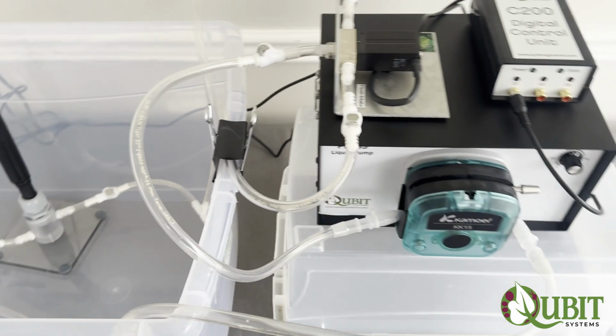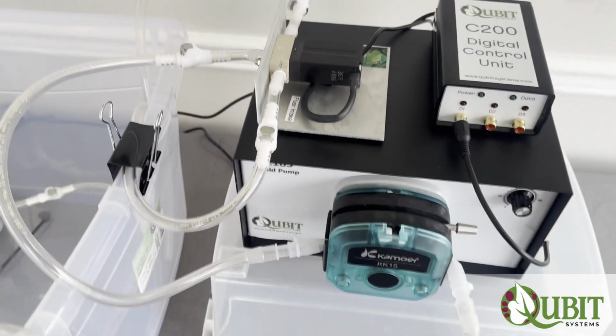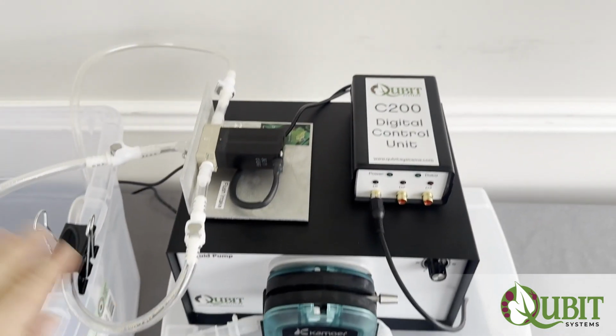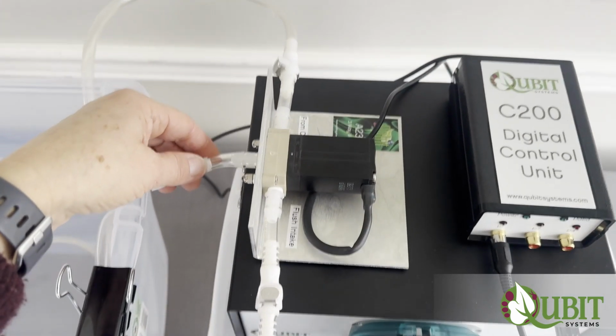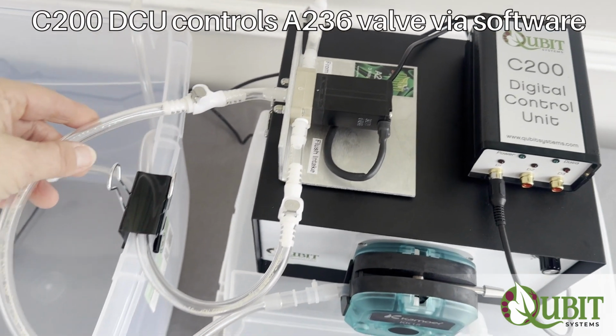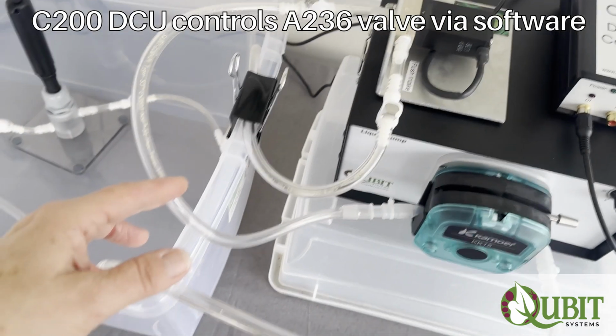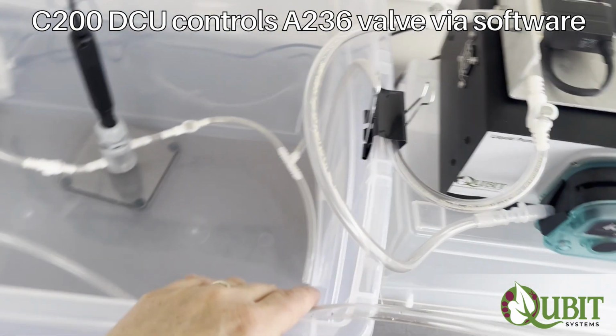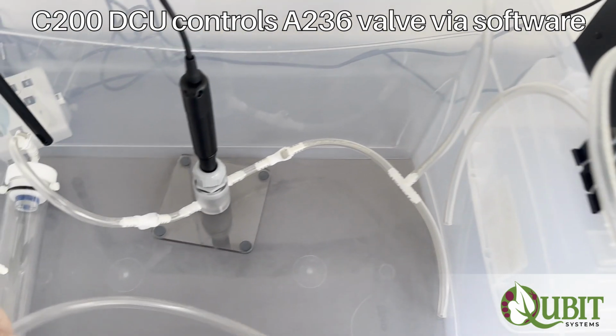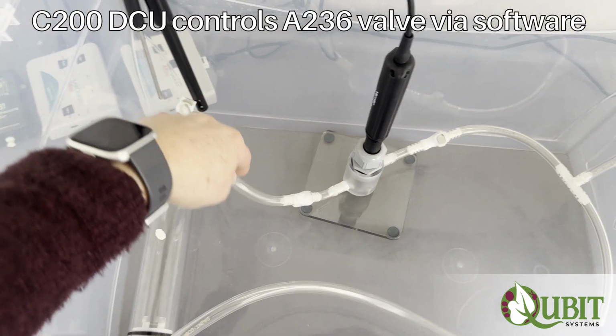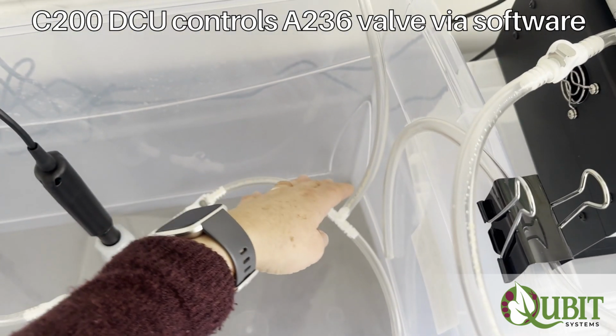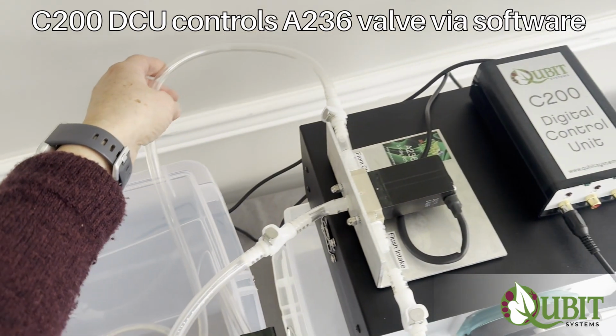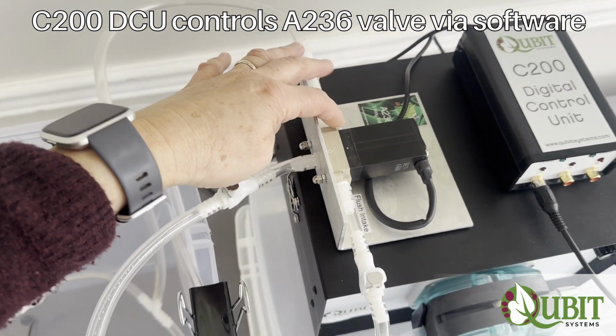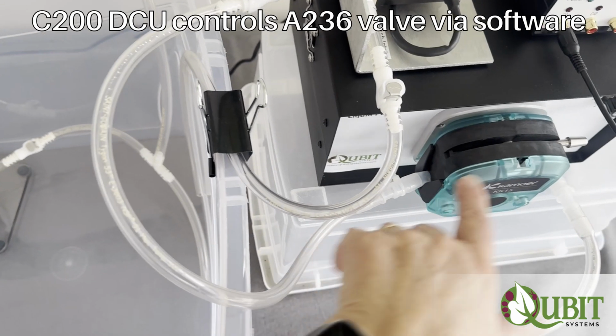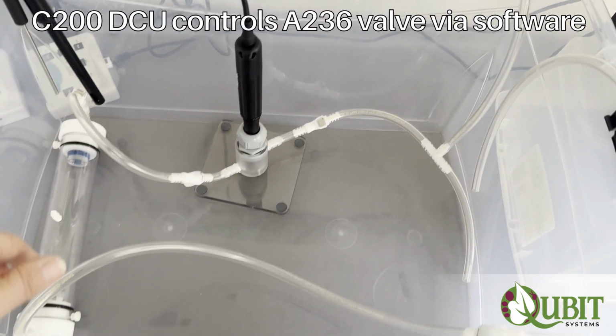The system comes with a liquid pump, a peristaltic liquid pump, which is connected to a three-way valve. This three-way valve redirects the way that the water flows in this package through this pump, and it either brings the water to the chamber with the animal and then the DO probe, and from the DO probe it carries back to the three-way valve, and it goes in a circular way back to the chamber. So during that time the system is closed and the water circulates through.